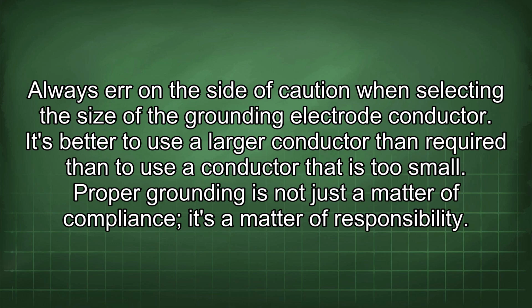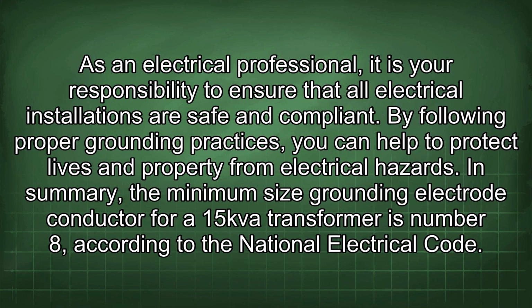Proper grounding is not just a matter of compliance, it's a matter of responsibility. As an electrical professional, it is your responsibility to ensure that all electrical installations are safe and compliant. By following proper grounding practices, you can help to protect lives and property from electrical hazards. In summary, the minimum size grounding electrode conductor for a 15 kVA transformer is number 8 according to the National Electrical Code.